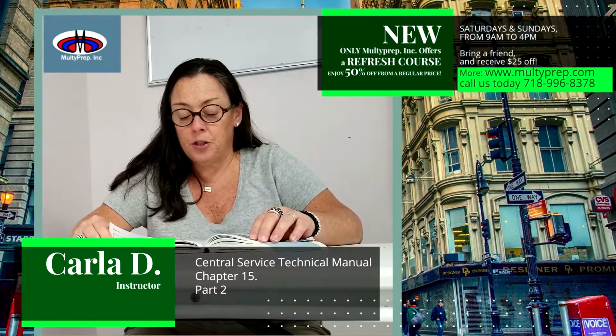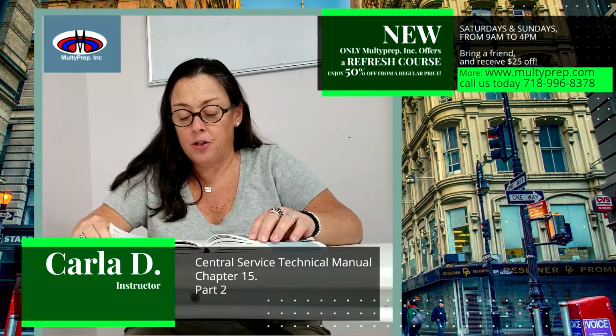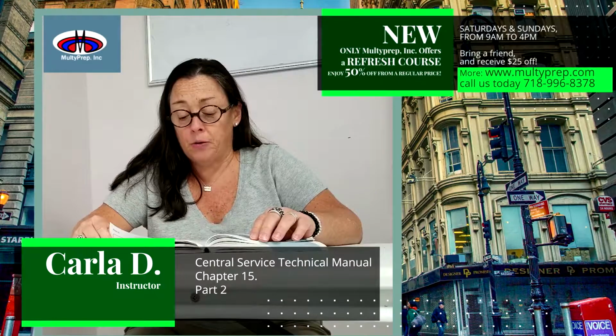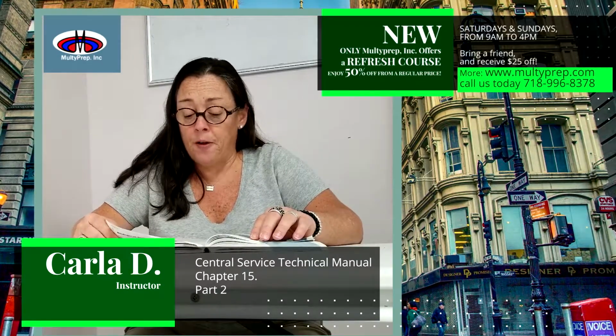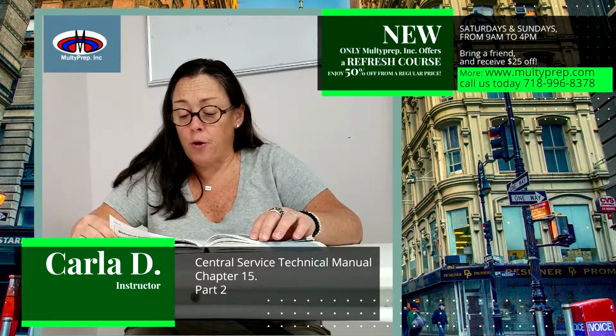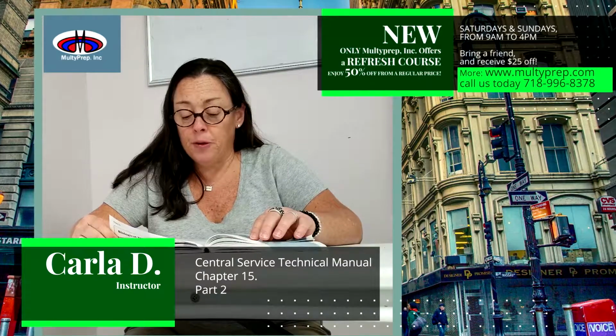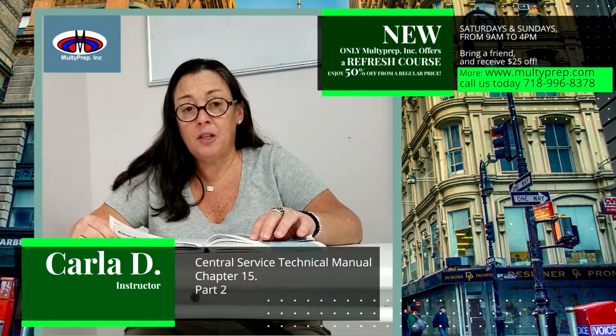ETO sterilization is compatible with a variety of packaging materials, including paper, plastic, or Tyvek peel pouches, approved fabric wrappers, medical crepe paper, polypropylene, and most container systems. Note: aluminum foil, cellophane, nylon films, polyester, PVC plastic films, and styrofoam should not be used.